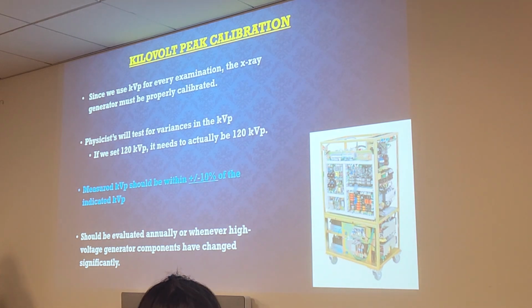Alright, any questions on the kVp calibration? So theoretically, if you're shooting at, let's say, 80 kVp, you could be shooting anywhere between 88 and like 10% under, even if you set it at 80. So 10% below or 10% above? Yeah, that's your range to still get the same optimal image. And how does that affect our math whenever we're trying to increase or decrease the contrast? Like if we thought we were shooting at 80, but it's really at 88. Well, that's why they do this test, to make sure that it stays within range. Okay. You won't do that. This is all medical physicists doing this. Cool.